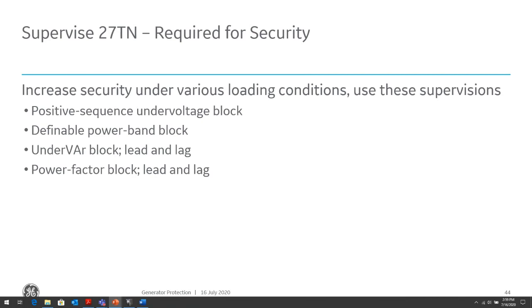We also need to block this protection when the generator is offline, because when it's offline, there's no third harmonic voltage being generated, so we don't want the element to trip. Obviously, it's not going to take the generator out, but it could prevent it from coming back online by locking the generator out.